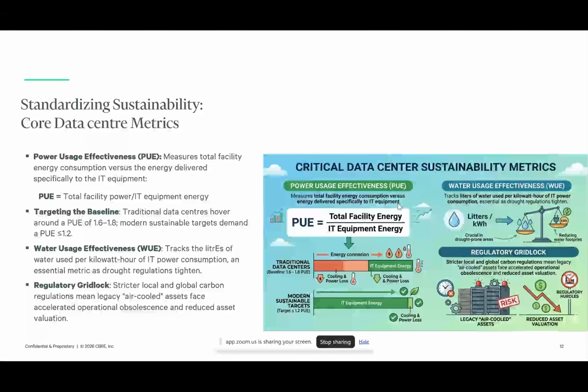There are two key metrics to keep in mind. Power usage effectiveness is a ratio of the total facility power, which is IT plus infrastructure, divided by the IT power. This helps us understand how efficient the capacity of the data center is. From a water usage perspective, we track the liters of water used per kilowatt of IT consumption, which is essential because it tells us the water consumption for the required cooling load.